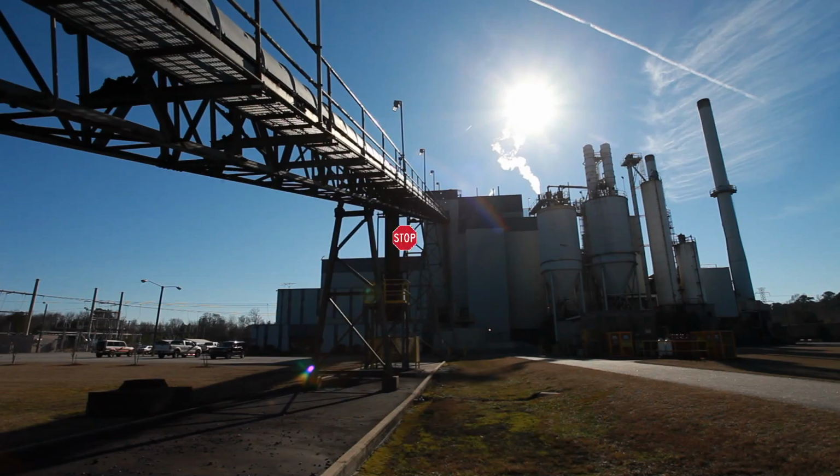The coal gravity feeds from the bunkers to the boilers. The coal is burned to provide the heat required to convert water into high temperature and pressure steam. The boilers heat up and some of the ash forms clinkers on the boiler walls and grates. The hazards are heat, boiler gas, possibly steam from a tube leak, pinch points, rotating equipment, ergonomics when raking grates, and manual exhaustion, which are a few of the hazards of this job duty.